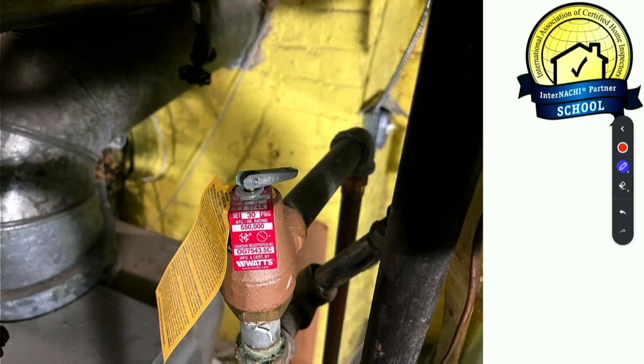Well, I hate to hear the conversation about breaking on testing with these sorts of things. So, at least with water heaters, which is where I typically see a temperature pressure relief valve, I usually just do a visual check to see if there is corrosion or signs that it has been leaking in the past, and just recommend a service for that. Fair enough. What about you, James? Same here, same as Jason.